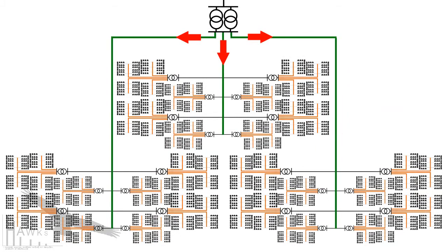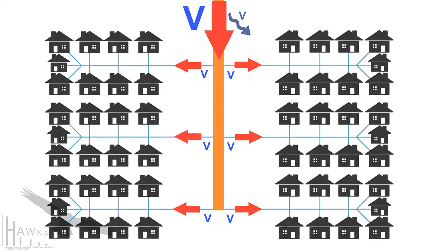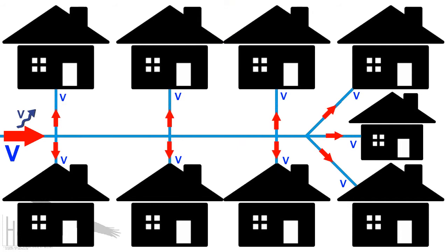Once the total current at the 33 to 11 kV transformer has been found, the voltage is set to a nominal value, and the potential at each junction can be found by subtracting the voltage drops that were calculated earlier. This two-step process provides us with voltage and current values for every level of the model.